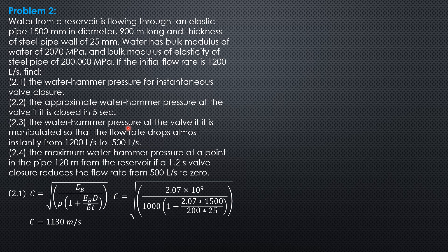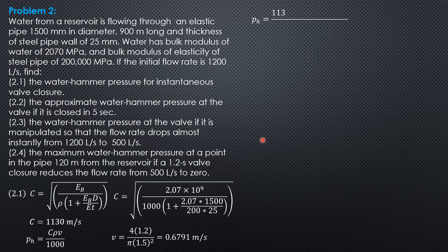For Part A, instantaneous valve closure: water hammer pressure pH = C × ρ × V / 1,000. Velocity V = 4Q / (π D²) = 4 × 1.2 / (π × 1.5²) = 0.6791 m/s. Substituting: pH = 1,130 × 1,000 × 0.6791 / 1,000. The water hammer pressure for instantaneous valve closure is 767.4 kilopascals.